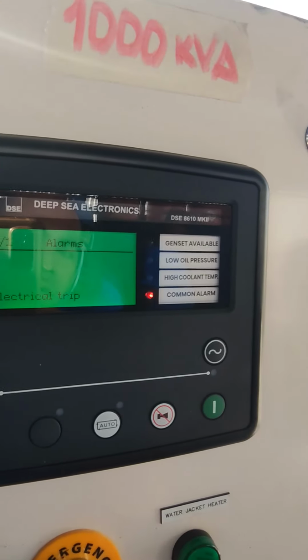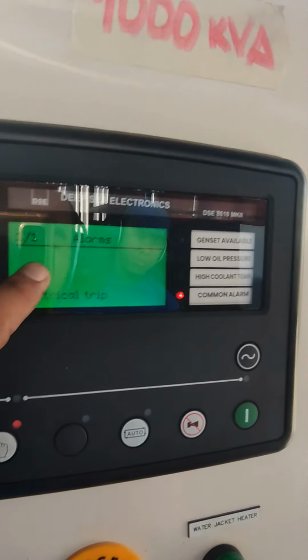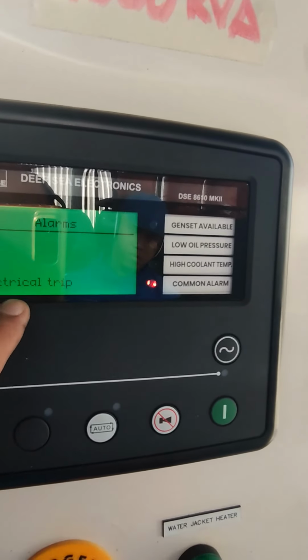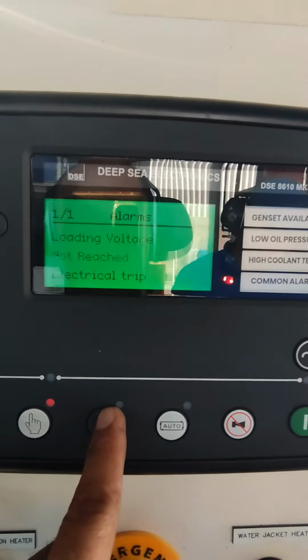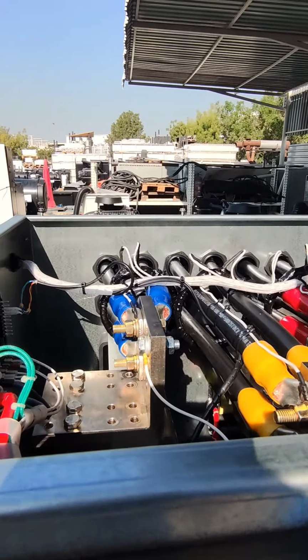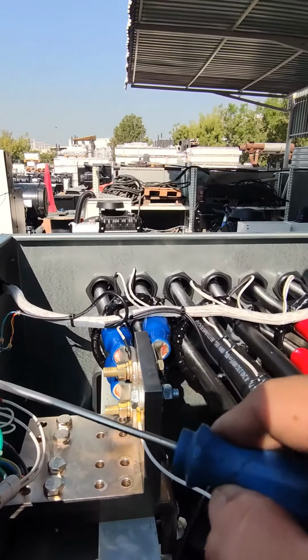So now we have only one alarm, 1/1. So we have the loading voltage. So now we need to adjust the voltage. That means the oil pressure low is fixed already due to our lost connection for the body connections. So now we're going to start and adjust the voltage from here.